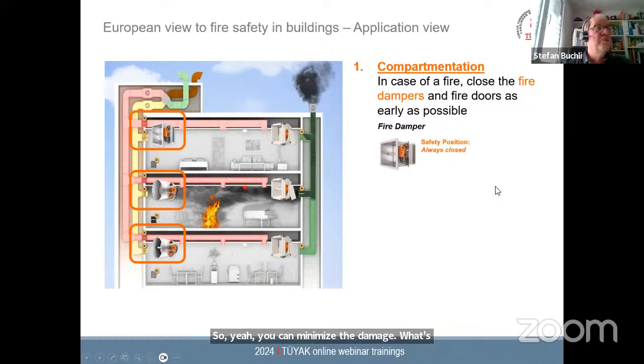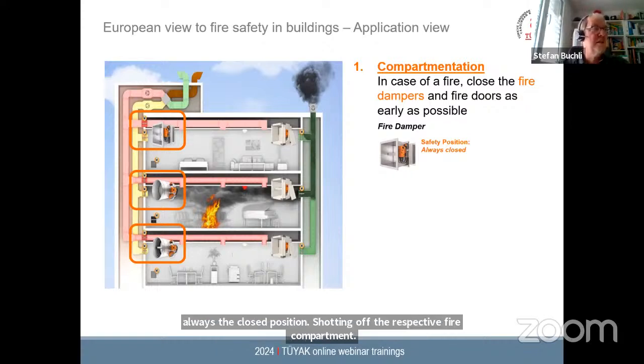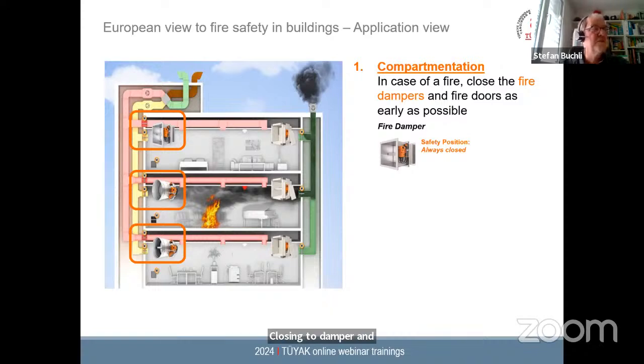What's also important to mention here, if you look just at the fire damper which you see here on the right-hand side, is that there is one safety position of a fire damper. It's always the closed position, shutting off the respective fire compartment, closing the damper and blocking the transfer of smoke or fire through the ductwork. So it's always the closed position, and that is also the reason why spring return actuators are always used on fire dampers. So, spring return closed.